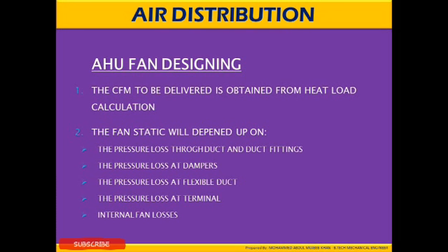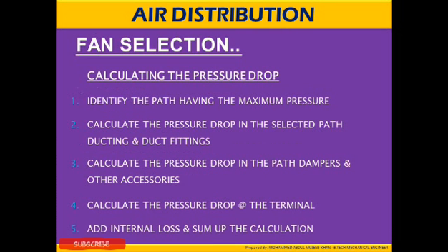AHU fan designing. The CFM to be delivered is obtained from the heat load calculation. The fan static will depend upon the pressure loss through duct and duct fittings, the pressure loss at damper, the pressure loss at flexible duct, the pressure loss at terminals, and internal fan losses. Fan selection.